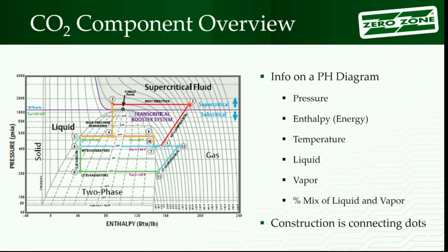You have the opposite for a condenser. I start out over here. It's got a lot of energy. It's hot. As I run it through the condenser, or in this case the gas cooler, I'm going to cool that down. The energy drops. I now have less energy in it. So I can reuse that refrigerant, start out with low energy, heat it up in an evaporator, and move it around.